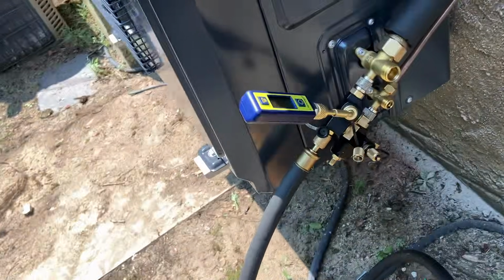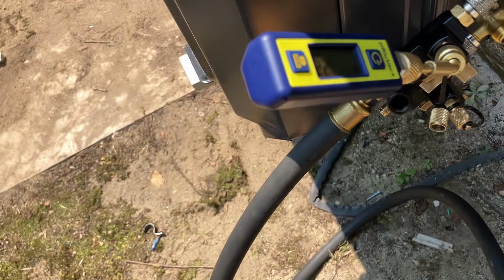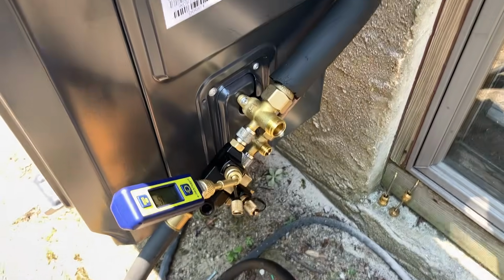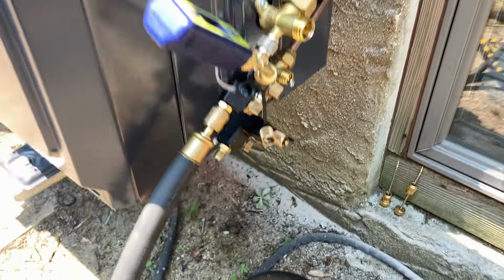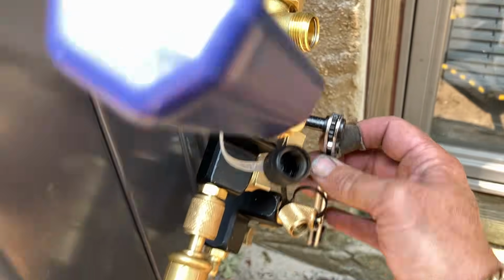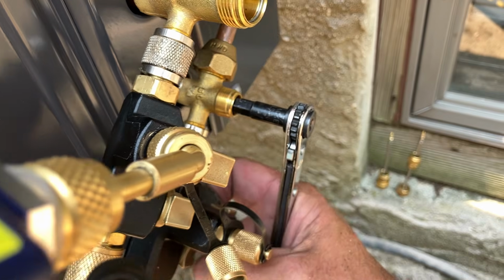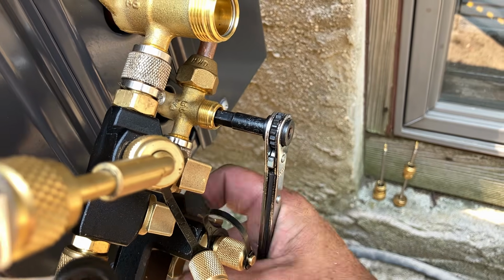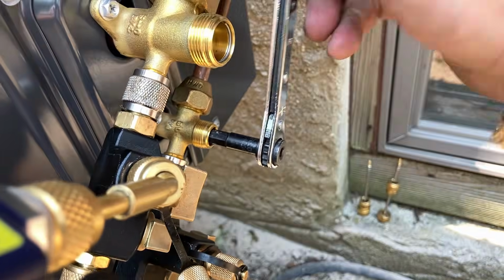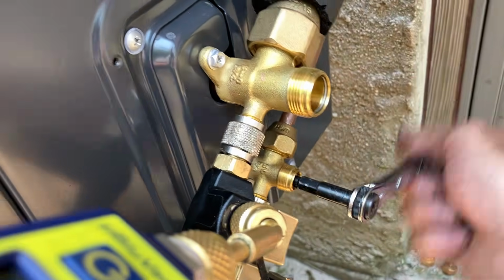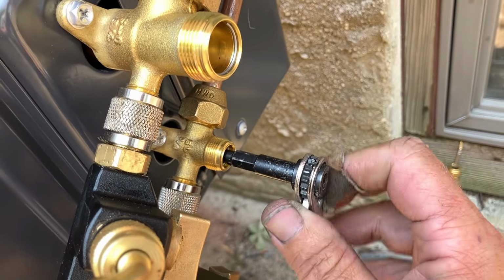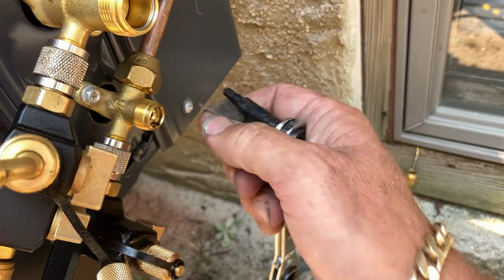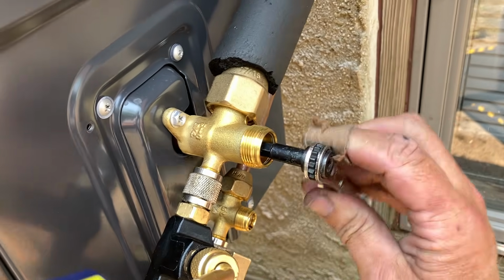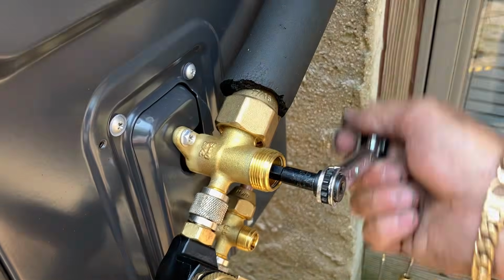All right, it's that time, folks. I'm gonna close off that valve and we're gonna dump the charge. Now, page 30 of the installation manual tells us to open up the liquid line valve first. So let's open that up right now. Let's open that valve. So we are opening this valve, and in the process, the refrigerant that's in the condensing coil, the outdoor unit, is being dumped into the line set and the evaporator coil.